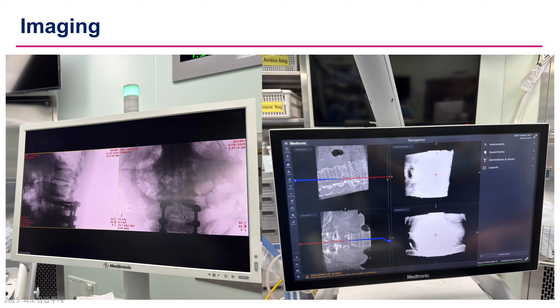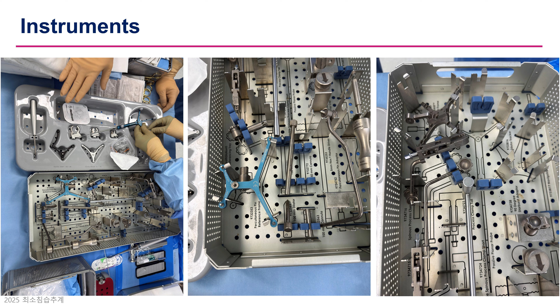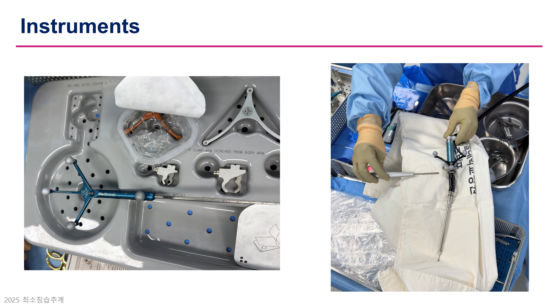Unlike pedicle screw fixation, navigation-assisted endoscopic surgery does not require many specialized instruments. In fact, apart from the screw set, all we need are universal adapters for the probe and burr. On the left, you can see the navigation probe, which is used to identify the laminectomy site and confirm disc location. On the right, the burr system is shown with a universal frame attached. This allows us to track the exact position of the burr tip during bone work.